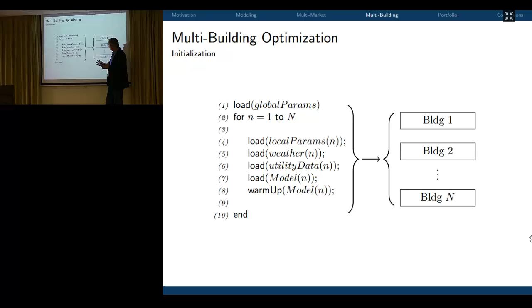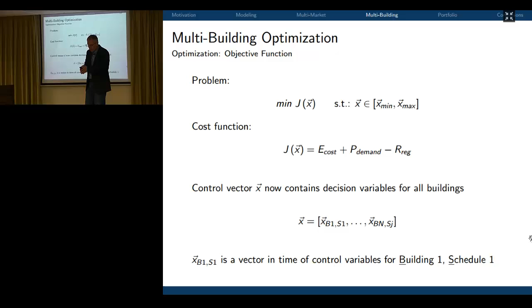Now the multi-building optimization cost function is the same as before: it's energy cost plus demand minus regulation revenue. But now the control vector is not for one building, it's for multiple buildings — B1 means building 1, and Bn is building n. For every building, we can have different optimization schedules, so the flexibility is now at hand to optimize multiple buildings. In each building we can optimize, for example, room temperature set points, chilled water temperature, or other things.